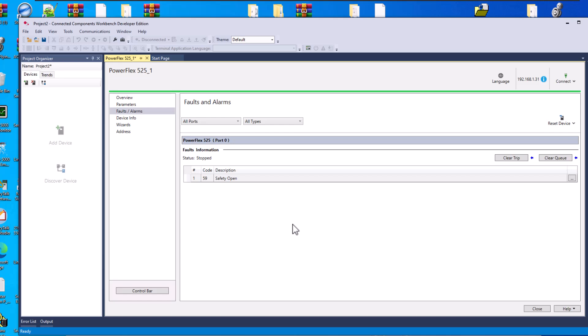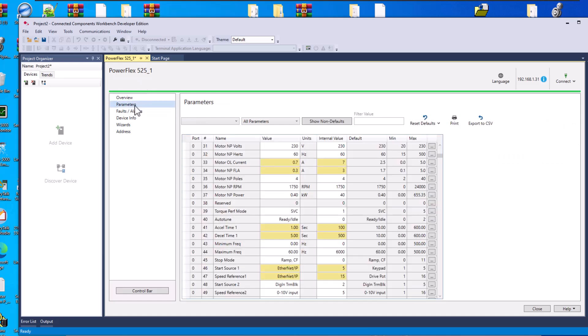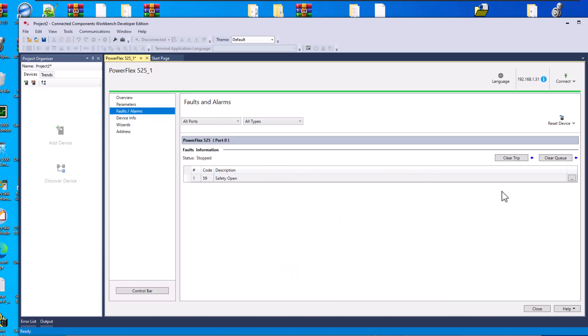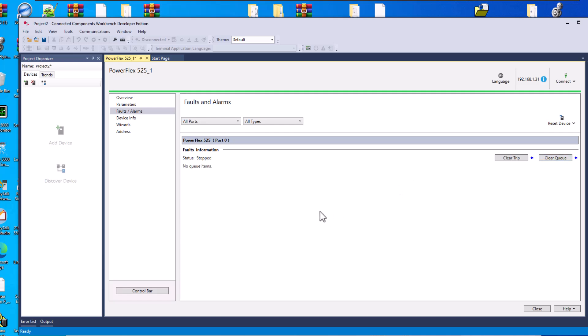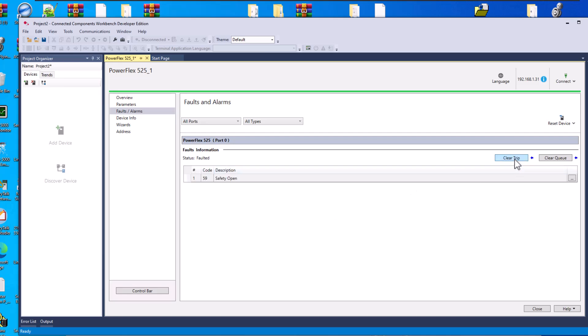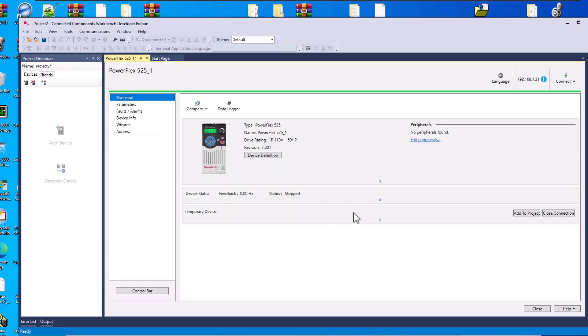You're going to have a splash window up here, you're going to have all your parameters, you're going to have everything in there. Then you go to faults - if you're having problems, you can see all the faults and all the history of the faults. If you're saying okay I'm going to start from here and move forward, if I think I fixed the problem, you can clear the queue and see if it happens again. If you leave overnight and think you got the problem fixed and the problem comes back, you can go back and look at the history. It does keep a good history of what happens.